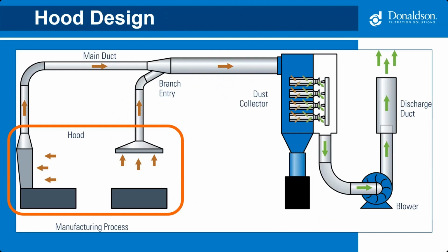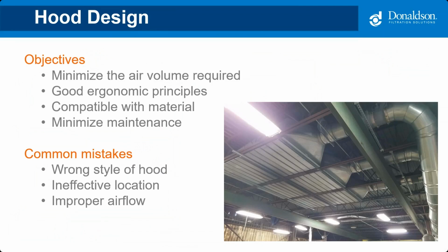Okay, so back to our system diagram here. The first component that we'll be talking about is the hood. This is a critical component of system design that will allow for airflow containment and a collection of the fugitive dust. So a well-designed hood is going to minimize the amount of airflow that's required to effectively capture and control that contaminant where it is released in order to protect workers. It should be designed with good ergonomic principles in mind, and it should be compatible with the material flowing through the work area. It should also be designed to minimize the maintenance and other activities that may disrupt the process.